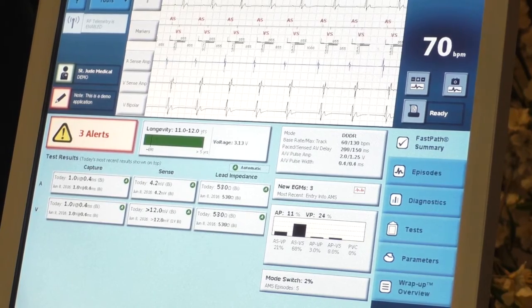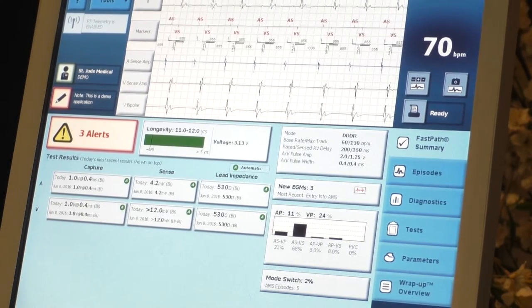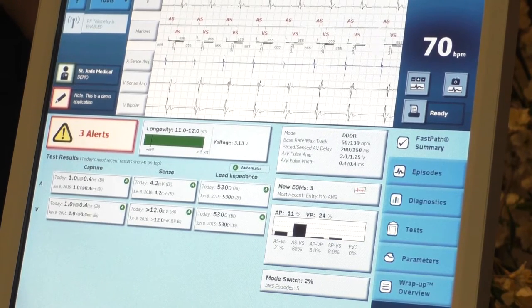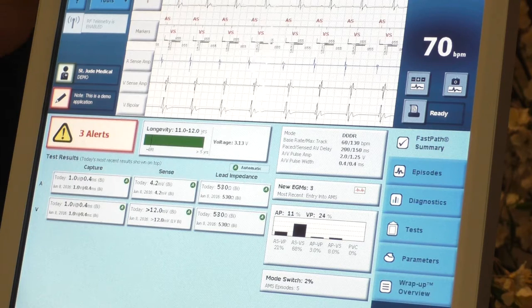On this demo patient, the signal is all pink. The demo patient is on their own at 70 beats per minute. Their pacemaker is set at 60, so at 70 the pacemaker is kicking back and just watching. If there's a dip in the heart rate, the timer goes off and it'll force pace.